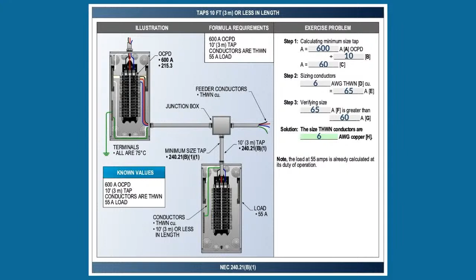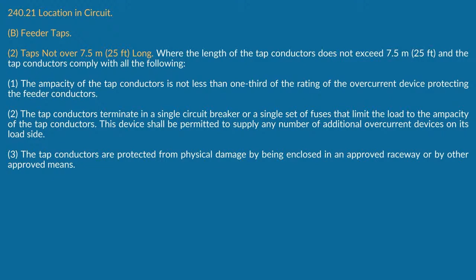And if you look right there in B2-1, it says those tap conductors are not less than what? 1/3. Okay. Now, you can read all this other stuff, but I'm just trying to show the calculation. So I'm looking at this. I have to take it at 1/3. All right. So if I look at this, you're going to see we're doing a 600 amp again. I take it at 1/3. That's going to give me 200 amps.